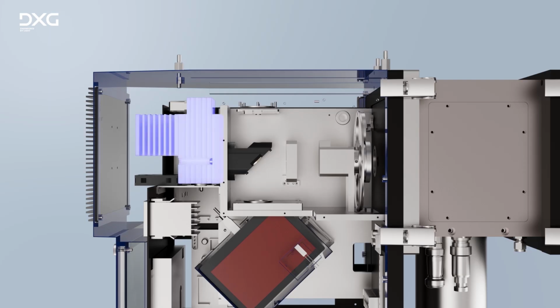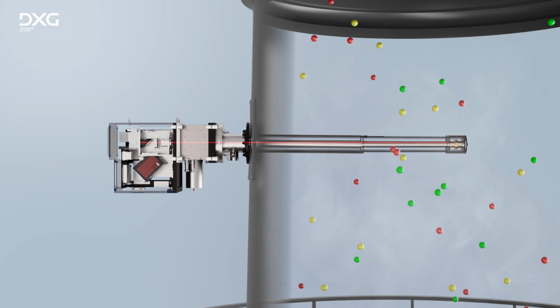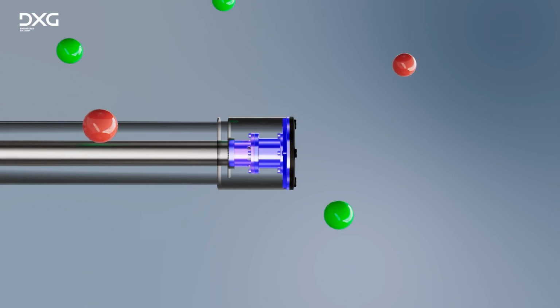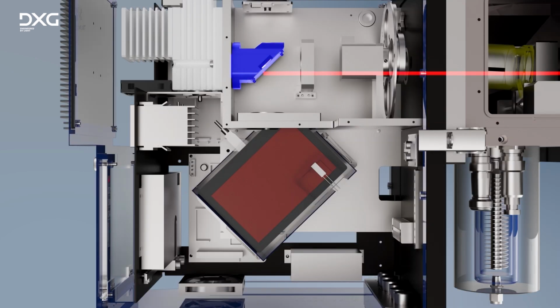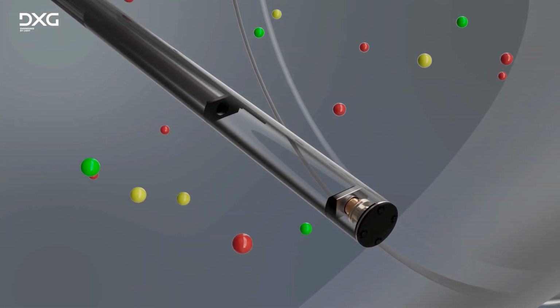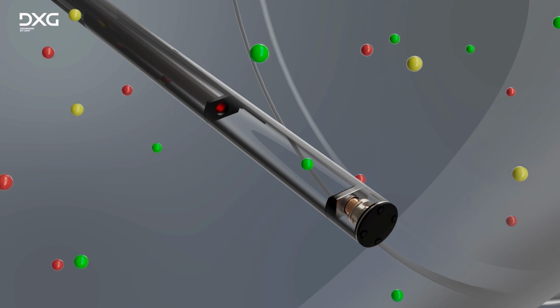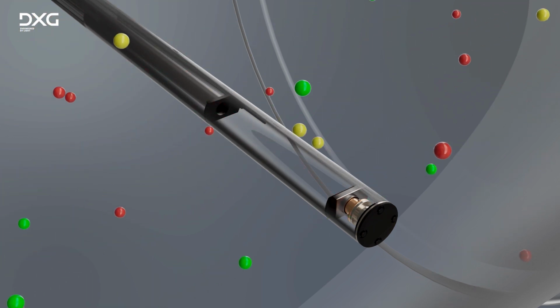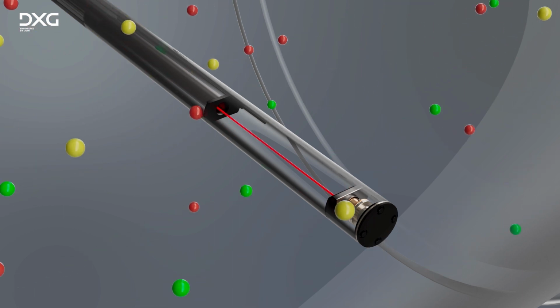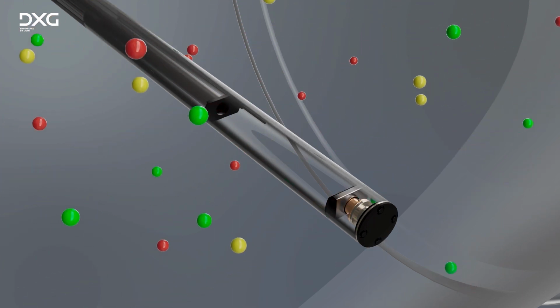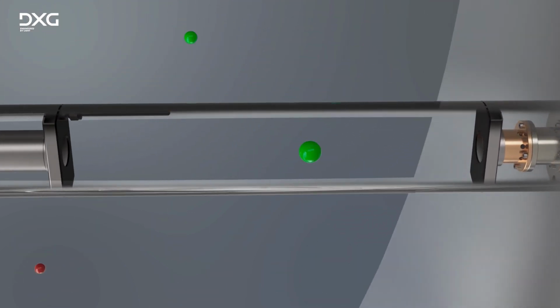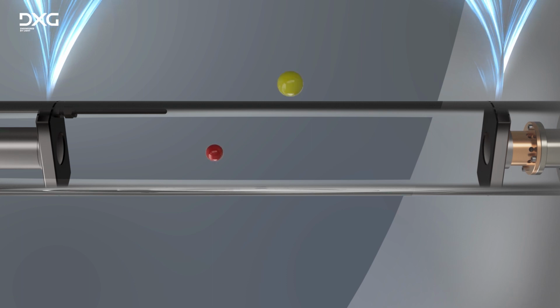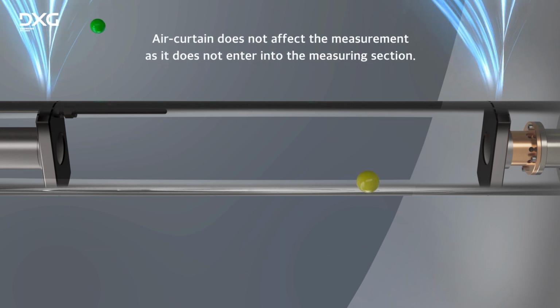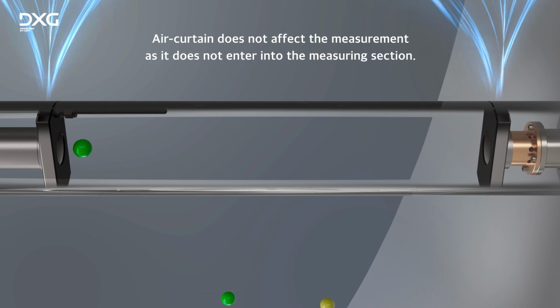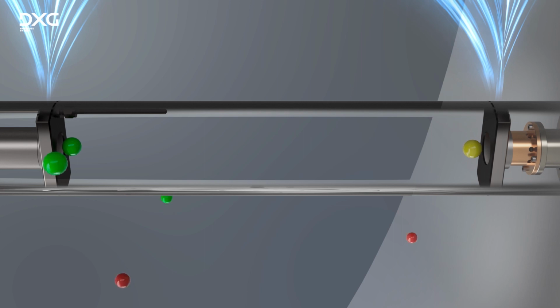Once the analyzer unit is mounted into the chimney, the light emitted from the UV lamp travels through the gas flowing through the measuring section of the probe, and then travels back to the main unit for analysis by the spectrometer. The amount of absorption of the light that was initially irradiated and the amount of absorption of the light that was returned differ by the concentration of the gas components being measured. This difference is used to calculate the concentration of the substance. In this process, floating matter inside the chimney can cause contamination in the optics of the analyzer. In order to prevent such contamination, a purge blower unit is provided to prevent potential optics contamination by forming an air curtain.